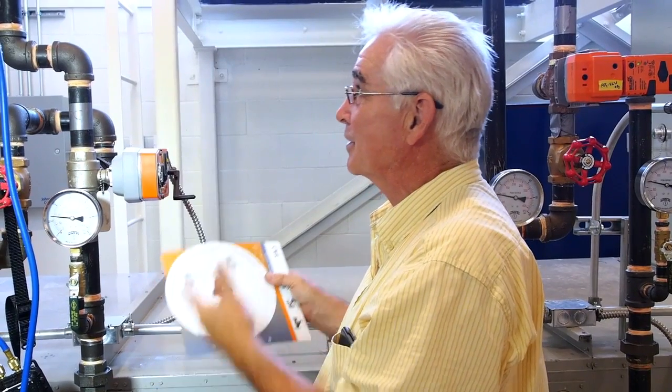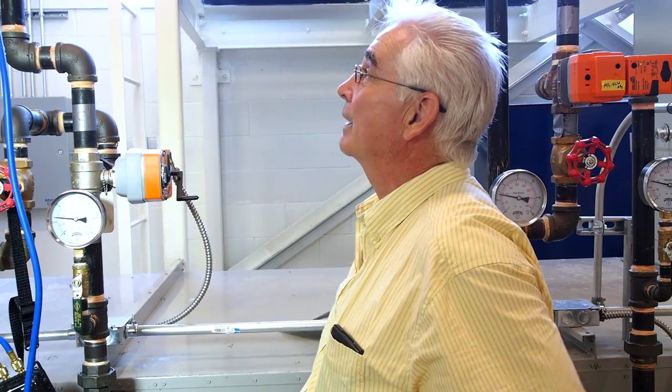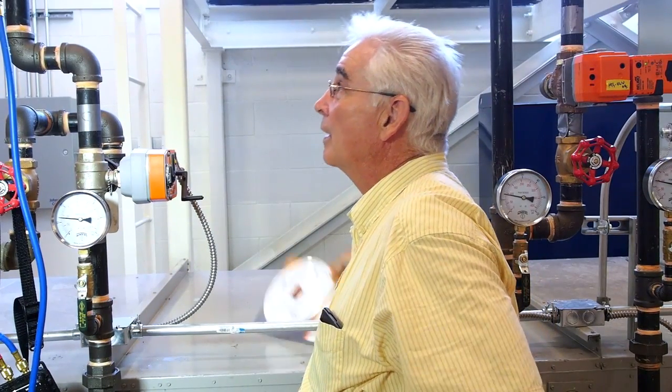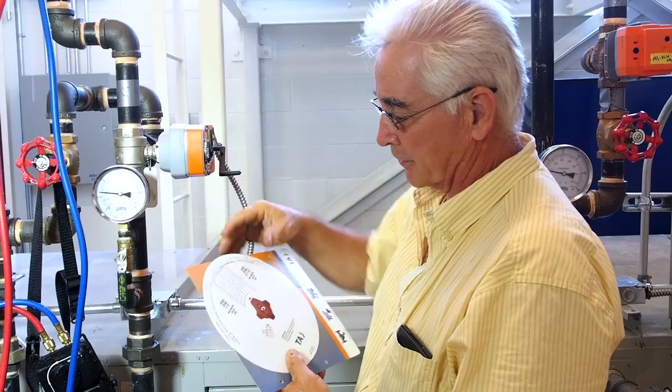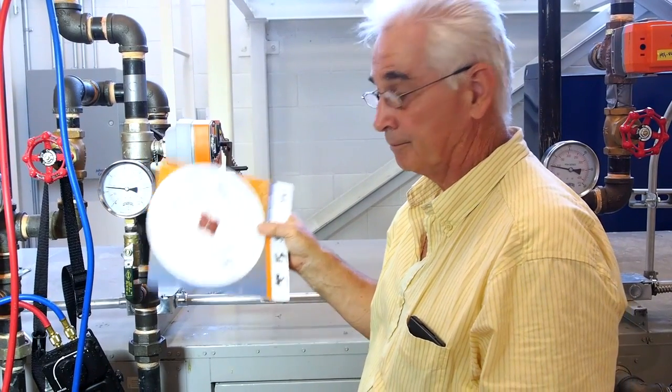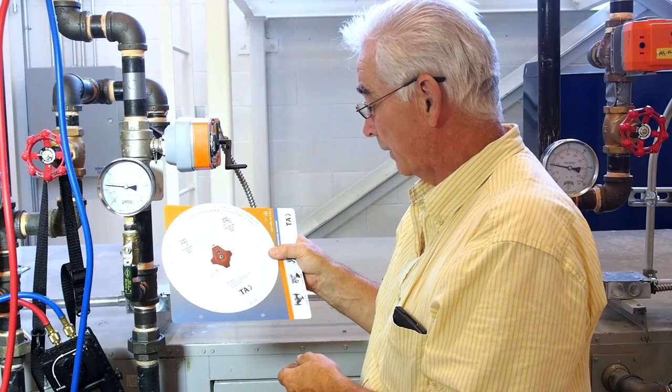That's how simple it is to balance with circuit balancing valves. It's just a matter of measuring the differential pressure and knowing what the hand wheel setting is and having the proper wheel.